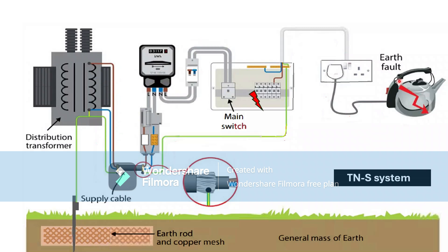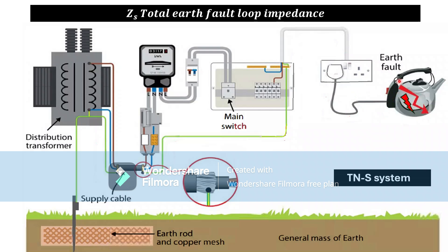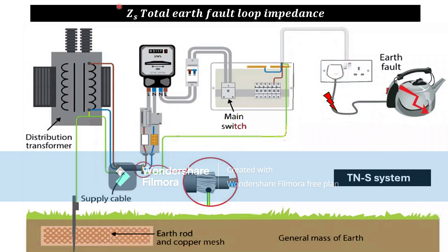This fault path resistance needs to be as low as possible so that the breaker can trip on time. This whole path is known as Zs — the total earth fault loop impedance. That means the resistance of the line and CPC from the supply transformer to the final point of the sockets or lights. The furthest point gives the highest resistance, and that's where you measure Zs.